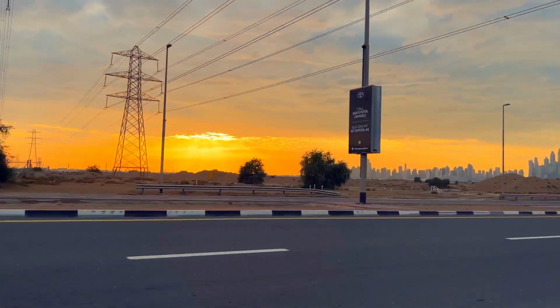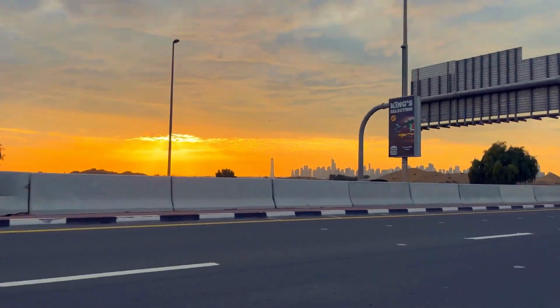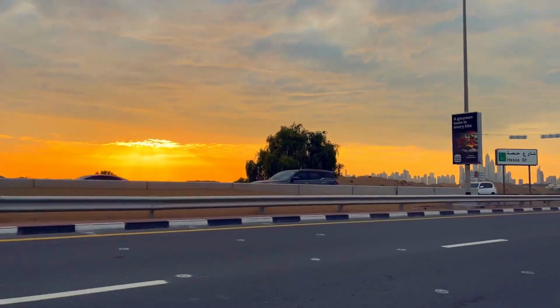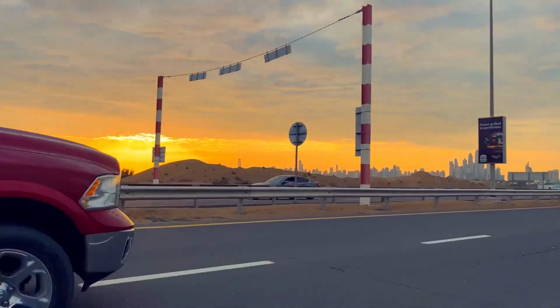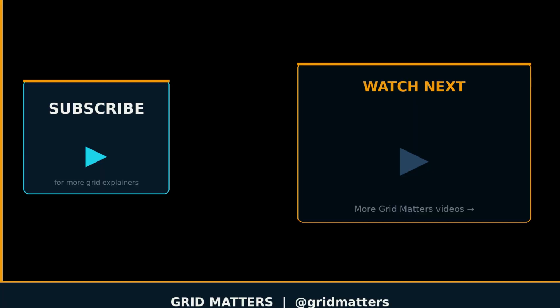As the grid fills up with solar panels and batteries, which connect through electronics that barely produce that surge at all, the spike is getting smaller. The fault is still there, but the flag it used to wave is fading, and a substation can only protect what it can still see.